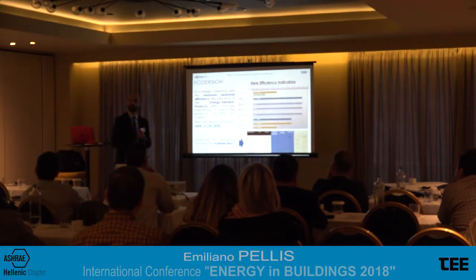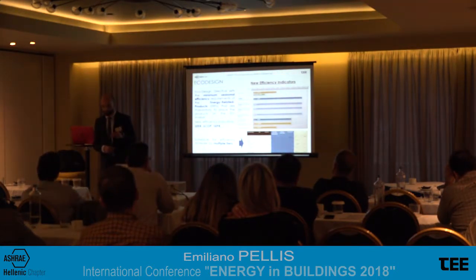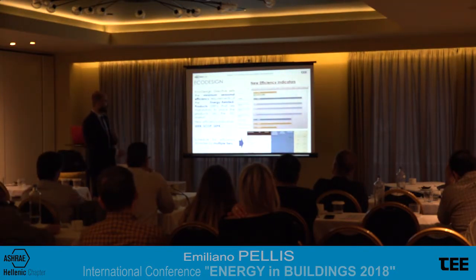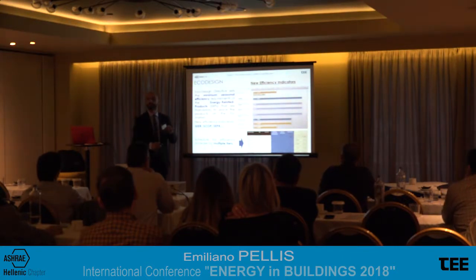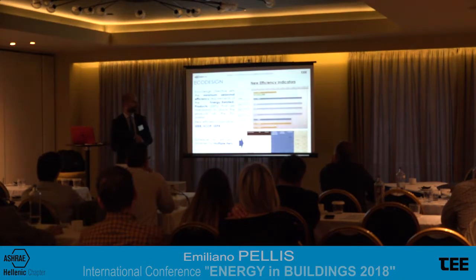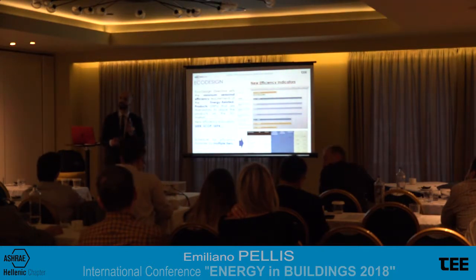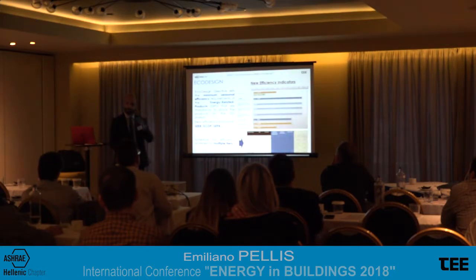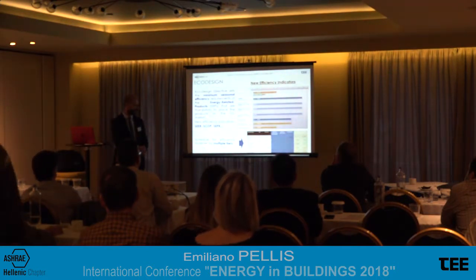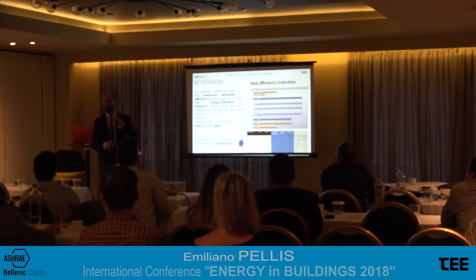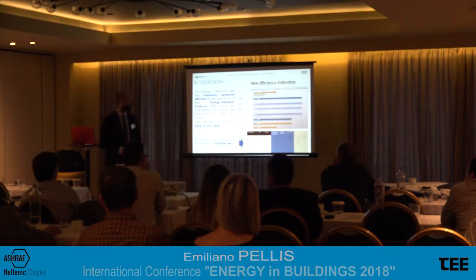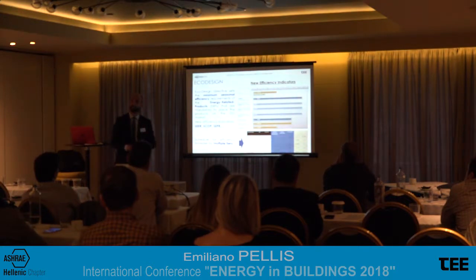Further to this, the regulation has introduced some new energy efficiency indicators, which are, for example, the SEER for chillers intended to operate in comfort cooling applications, the SEPR, which represents the seasonal energy efficiency for chillers intended for process cooling applications, and the SCOP, the seasonal COP for a heat pump, which is something new. In the past, we didn't have a seasonal energy efficiency indicator for the heat pump. As you know, the jump in efficiency on the market will be done over multiple years, in a gradual way. Every 3 years there is a step up. In such a way we increase the average efficiency on the market, giving the market and also the industry the time to react.